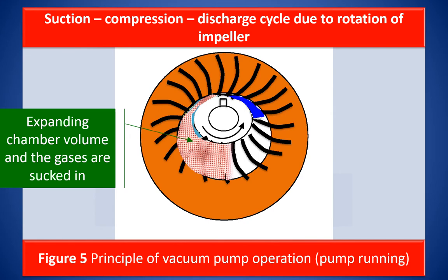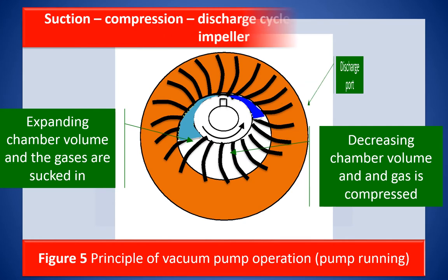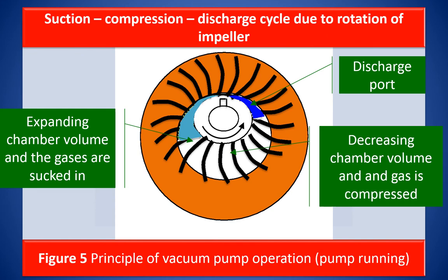The volume of the cell gradually decreases as the impeller continues to rotate. The gas is compressed and the pressure starts to increase until it reaches the pressure at the discharge port, which is close to atmospheric pressure. When the impeller reaches the discharge port, the gas from the cell is discharged. During continuous operation, the process of suction, compression, and discharge is continuously carried out, thus achieving continuity.